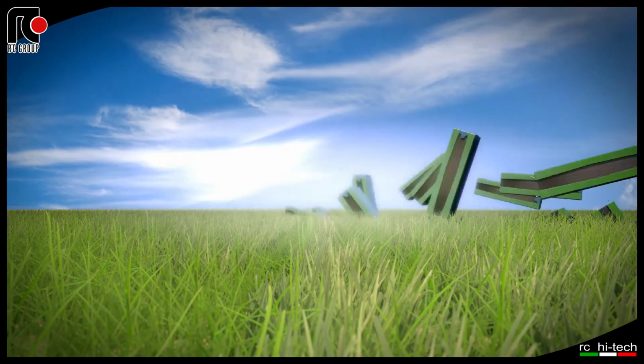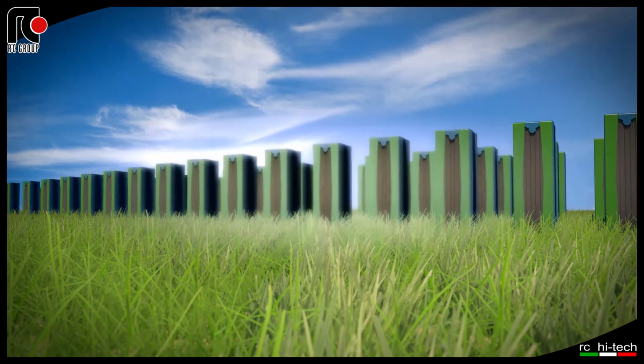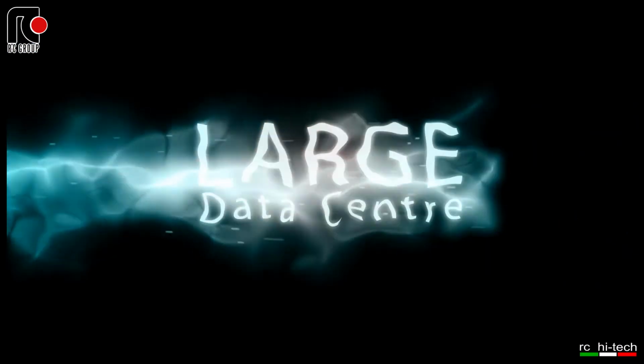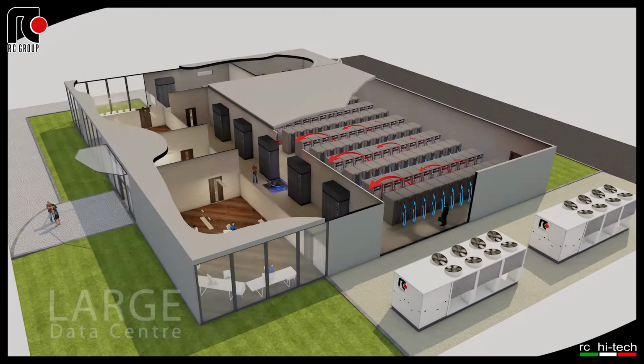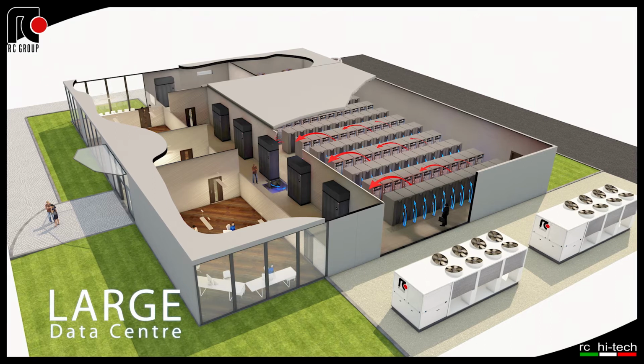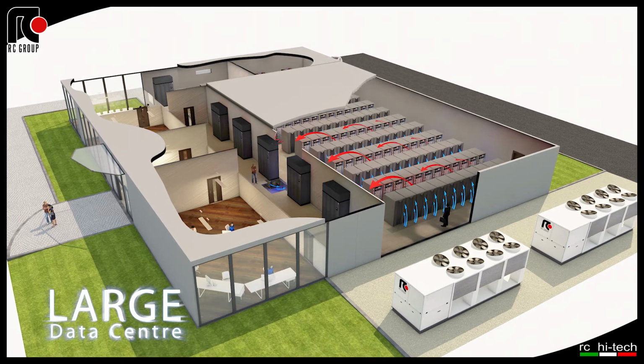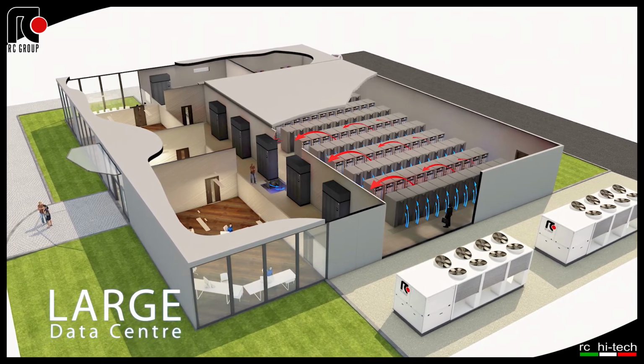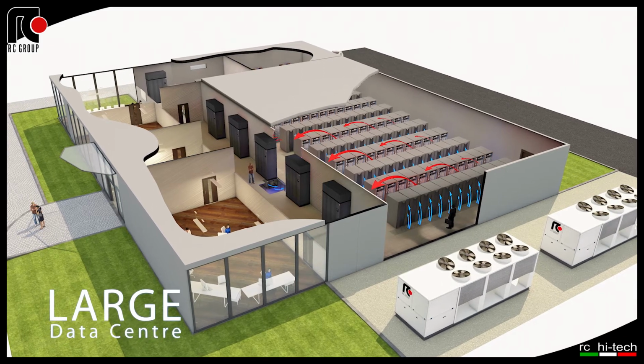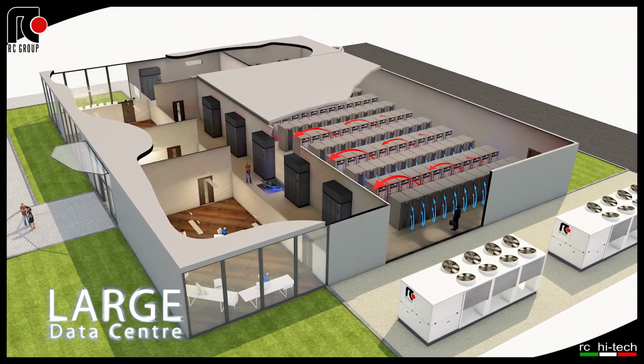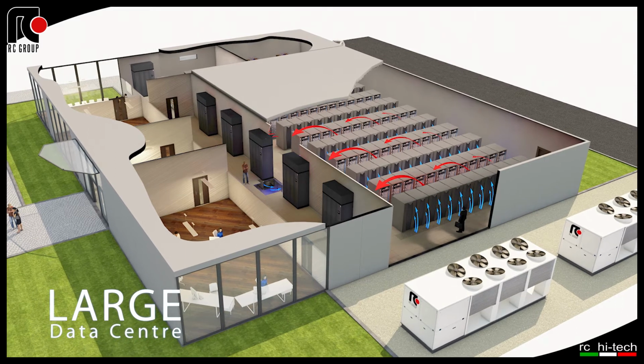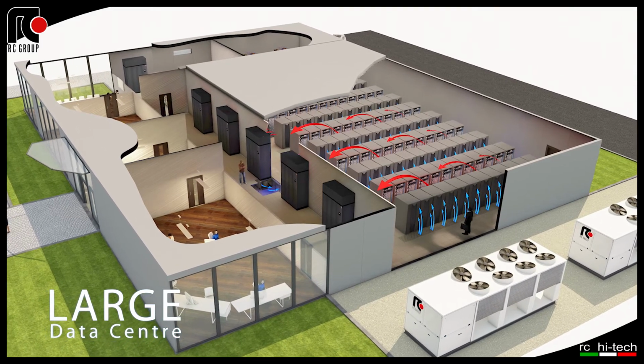Let's now analyze the green solutions developed by RC Group for each of the 3 types of data centers. Large data center. The best solution from energy point of view is the use of a chilled water system, mainly consisting of the air-cooled chiller, glycol-free, with free cooling sections, coupled with high-capacity chilled water precision air conditioners, next CWKL.